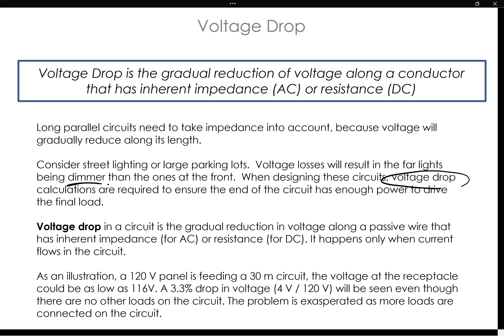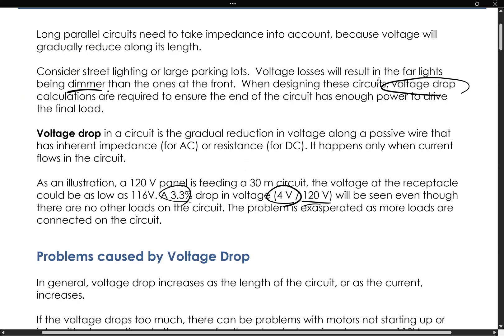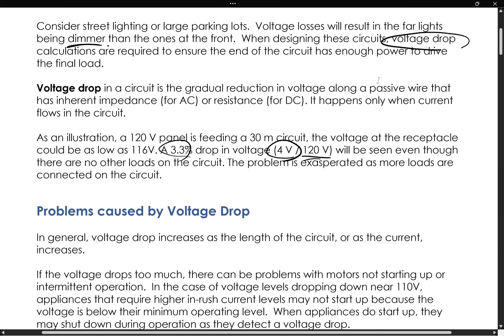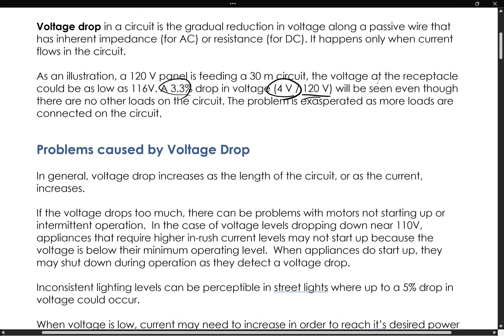That's a four-volt drop from a 120-volt panel — about a 3.3% drop in voltage. And that's not even accounting for any other loads in the circuit. This will become even worse as you connect more loads to the circuit.